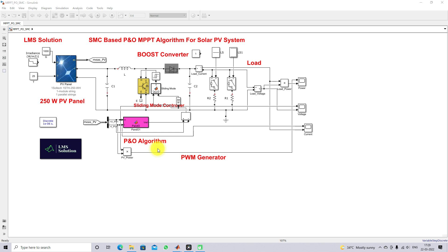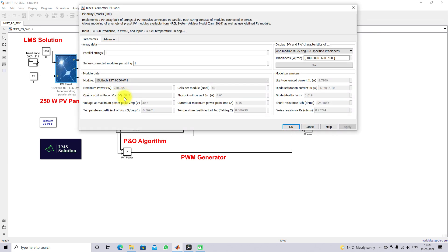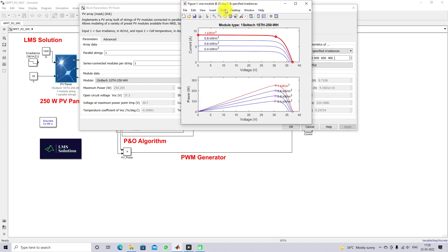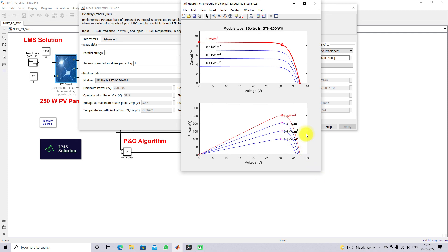This model consists of a 250-watt PV panel. The open circuit voltage of the PV panel is 37.3 volts. The voltage at maximum power point is 30.7 volts, the short circuit current is 8.66 amps, and the current at maximum power point is 8.15 amps. Here you can see the IV and PV characteristics of this 250-watt PV panel.